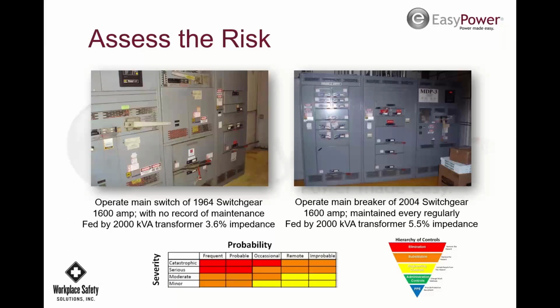you can make assumptions and do whatever you want, but main switchgear, if you're going to open these up, you'd have to have a full suit to do that if you don't know what the analysis says. You're going to still look at fault current and clearing time, and I'm going to go through the tables. You're going to use the NFPA tables, but if you can't use the category 2 table because your available fault current is higher than what's on the table, then you got to beef it up, and that would be using a full suit.